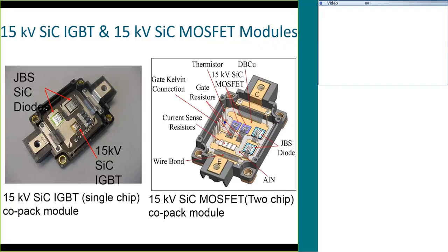If you look at the left picture here, this is the IGBT die, a 15 kV 20 amp die, 8.1 millimeter by 8.1 millimeter, and these are the two JBS diodes, which are 8 to 10 kV blocking and therefore connected in series for this 15 kV co-pack.